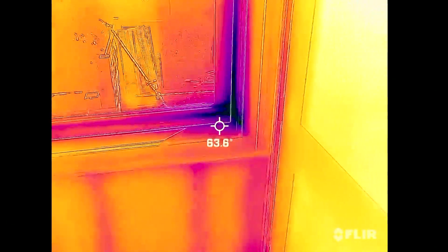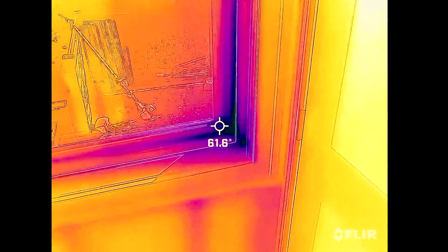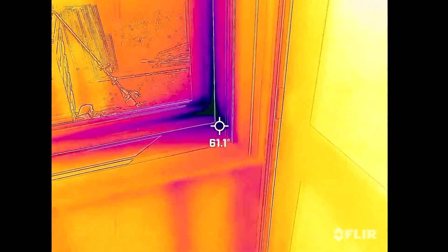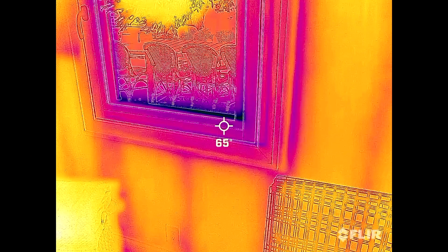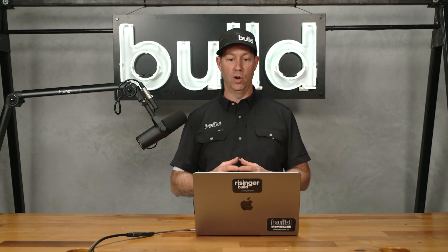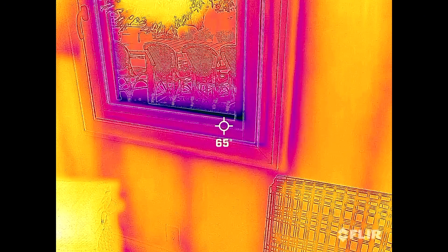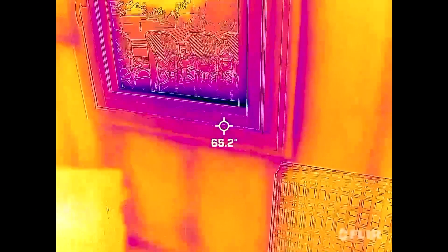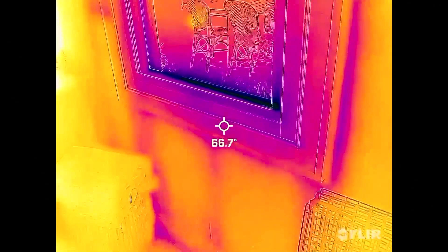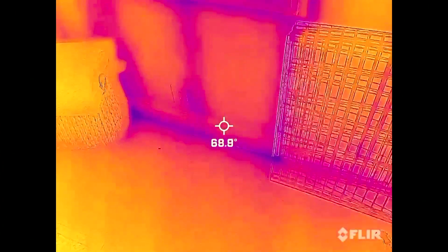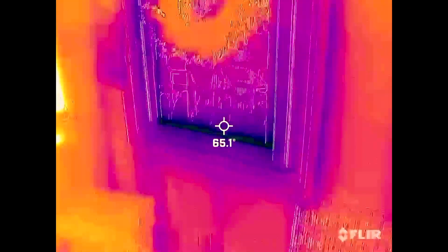In video mode on the FLIR, looking at that triple-glazed glass, there are really no surfaces much colder than about 50 degrees. Now for one other window on my house — this is a passive house certified window from a Canadian company called Fenster. It has Lightzone glass, which is extremely high-performing. This one is even warmer: the window frame coming onto the glass has really nothing below 62 degrees. With the dew point at 42 degrees, there's nothing that's going to cause any condensation whatsoever.